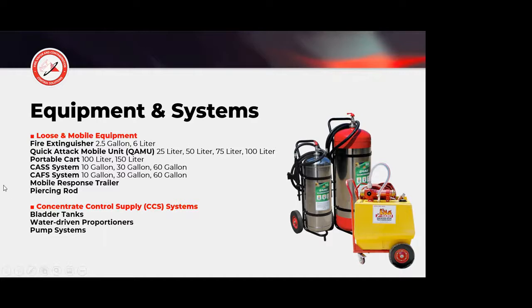And then we do supply CAF systems because we have Class A foam that's also fluorine free that will push through compressed air foam systems. We provide mobile response trailers, piercing rods, and then our concentrate control supply systems. We do bladder tank systems, water-driven proportioners, but we do have one balanced pressure pump system that is installed. In fact, that system was installed by Williams Fire and Hazard Control. It's outside of Memphis, Tennessee. Used their ratio controllers and pump proportioning systems. It was actually installed by International Fire Protection, but it's Williams Fire and Hazard Control equipment working in conjunction with the F500 on that rubber tire warehouse storage project.